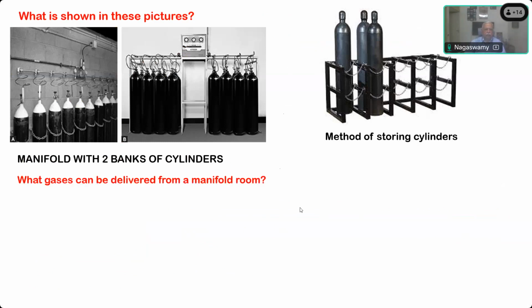So this is the correct method of storing the gases. What gases can be delivered from a manifold room? Is it only oxygen and nitrous oxide, or can some other gases also be delivered? Carbon dioxide, medical air. Medical air, very good. Nitrous oxide, oxygen, commonly we get it. That is agreed. Carbon dioxide is right. Medical air is also right. Any other gas? Entonox, cyclopropane. Entonox is not delivered from a manifold room. That much usage is not there.